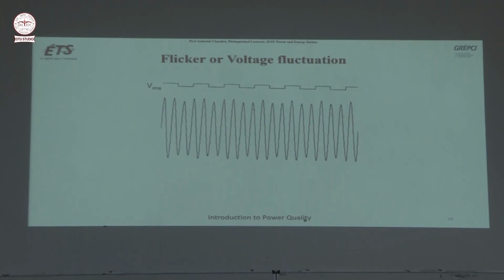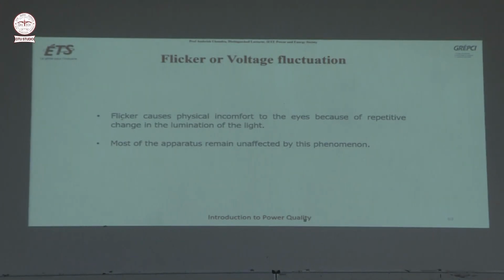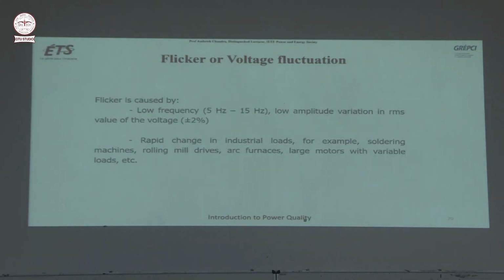Now coming to the flicker, voltage fluctuation. You can see the voltage like this, amplitude plus minus maybe 2. So this is called the voltage fluctuation or flicker. Flicker causes physical discomfort to the eyes because of repetitive illumination of the light. Most of the apparatus remain unaffected by this phenomenon. Flickering, you can see 5 Hz to 15 Hz variation, plus minus 2% of the voltage. In industrial load, for example, soldering machine, arc furnace, large motors with variable load may cause the voltage fluctuation.